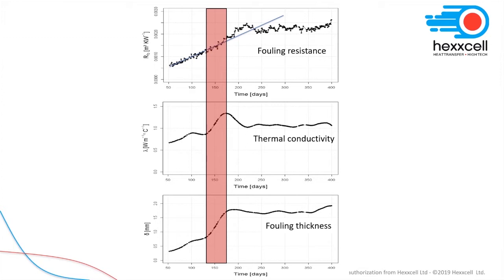It is interesting to see how, once the problem upstream of the heat exchanger has been resolved, the period in blue here, and the type of deposition going on inside the heat exchanger went back to normal, this is when the fouling resistance starts to show a deviation that can be misinterpreted as an issue.